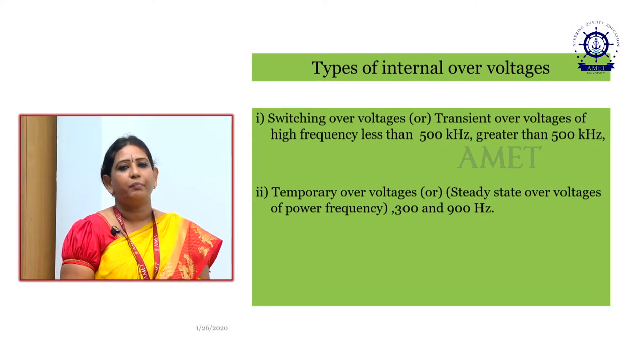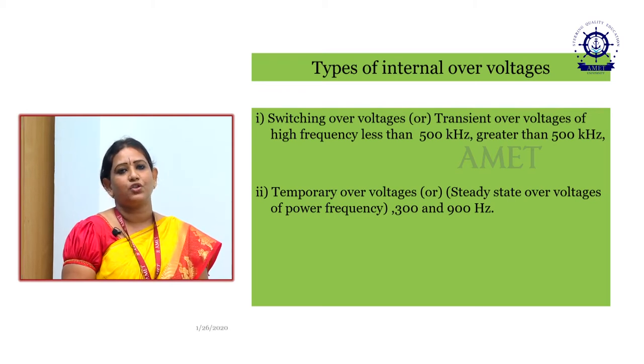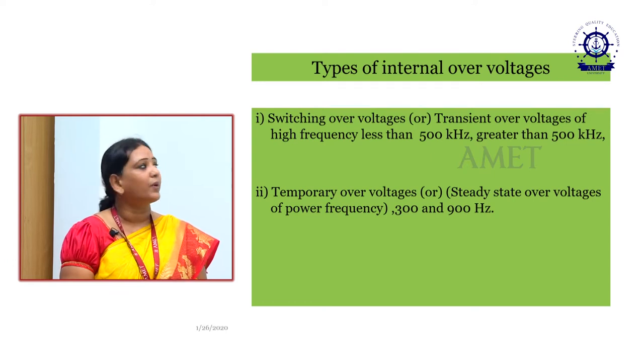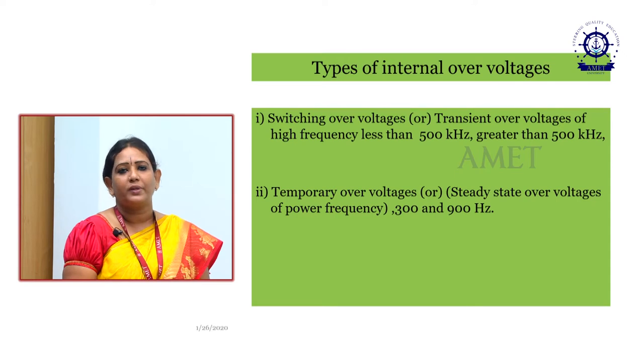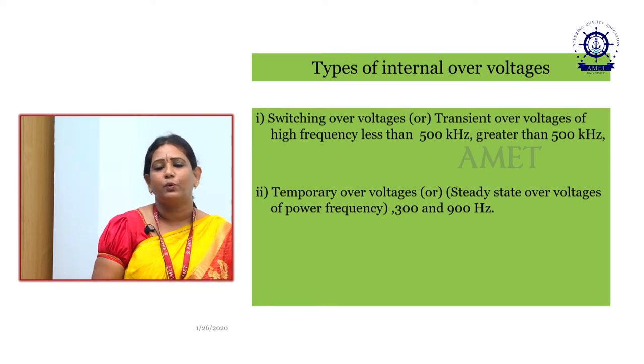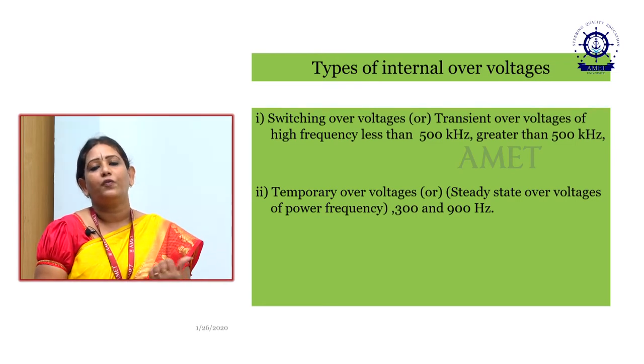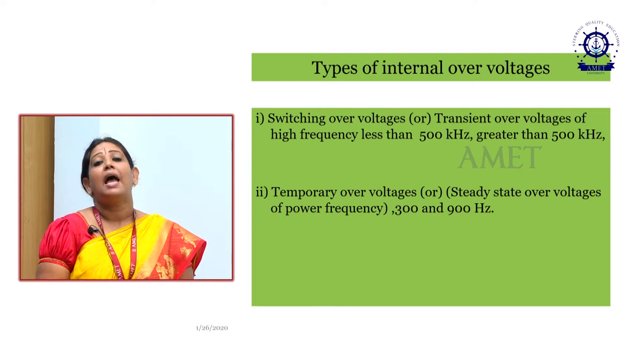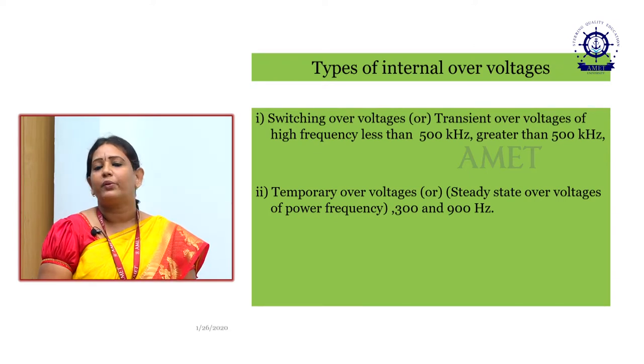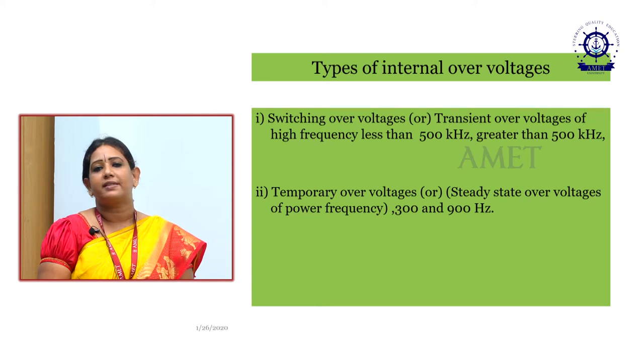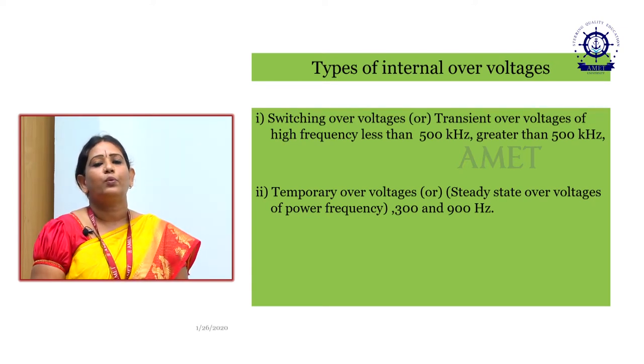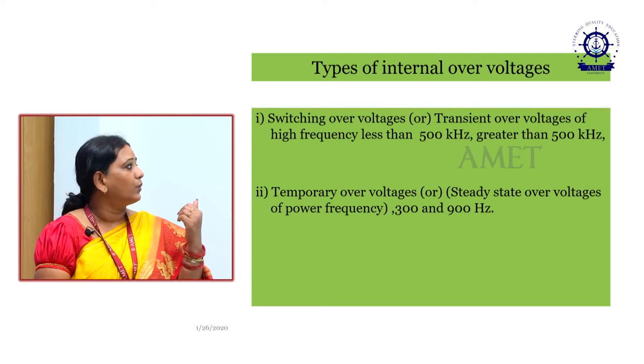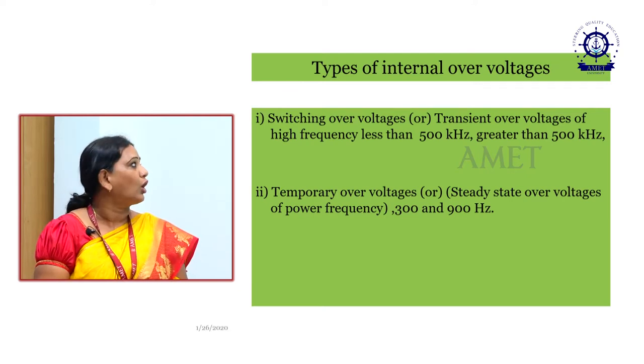Next, let us see a brief look at the types of internal overvoltage. There is a small classification of internal overvoltages. One is your switching overvoltage, otherwise called transient overvoltages of high frequency. I want to stress some more about the frequency related to overvoltage. Everyone will be thinking, what is the relation of voltage with frequency? We know our entire system is an AC network, an alternating current system, and the frequency is a major criterion. If the frequency is not maintained constant throughout the operation of the transmission system, the speed of the alternator may increase and an imbalance occurs in the network. So the entire system may be put under collapse conditions. We want to overcome such things, and these are all transients which have a high frequency of more than 500 kilohertz, and we call that a switching overvoltage.